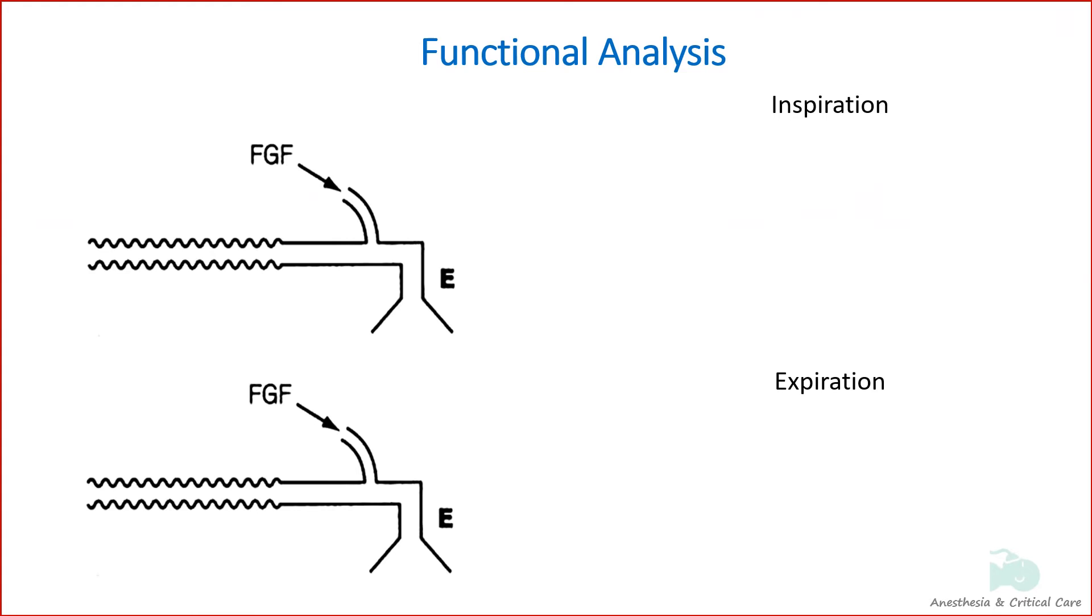Since the peak inspiratory flow rates are higher than fresh gas flow, gases are drawn from the reservoir limb during inspiration. If the reservoir limb capacity is less than the tidal volume of the patient, then air dilution occurs by dragging in the atmospheric air.